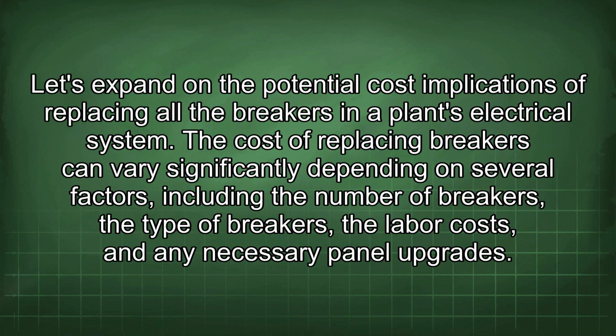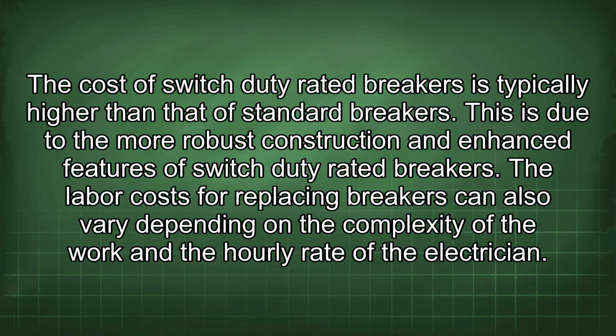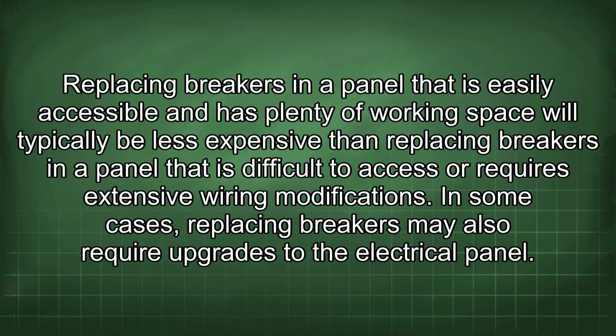Let's expand on the potential cost implications of replacing all the breakers in a plant's electrical system. The cost of replacing breakers can vary significantly depending on several factors, including the number of breakers, the type of breakers, the labor costs, and any necessary panel upgrades. The cost of switch-duty rated breakers is typically higher than that of standard breakers. This is due to the more robust construction and enhanced features of switch-duty rated breakers. The labor costs for replacing breakers can also vary depending on the complexity of the work and the hourly rate of the electrician. Replacing breakers in a panel that is easily accessible and has plenty of working space will typically be less expensive than replacing breakers in a panel that is difficult to access or requires extensive wiring modifications.